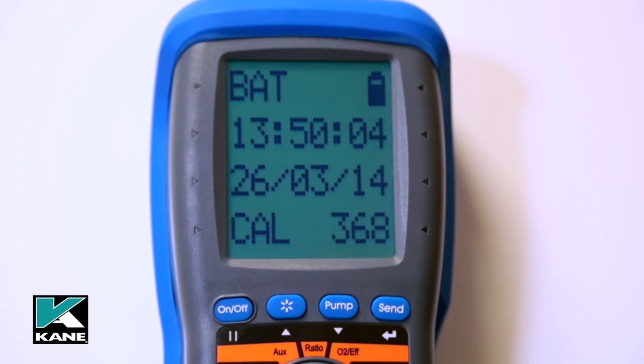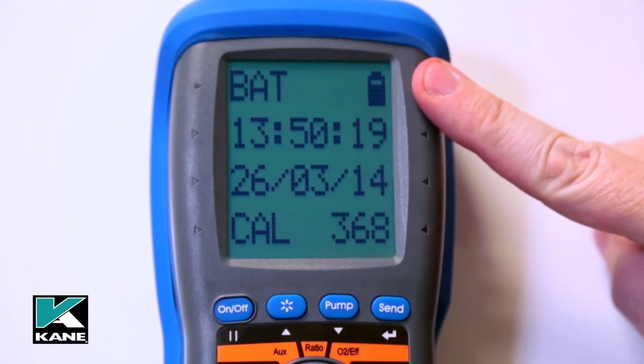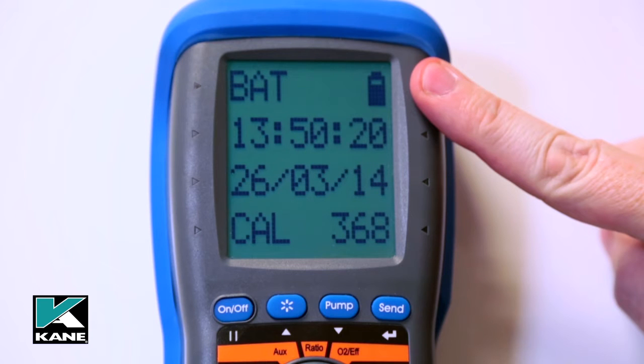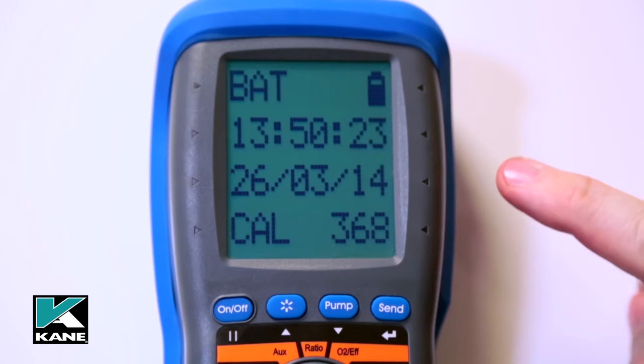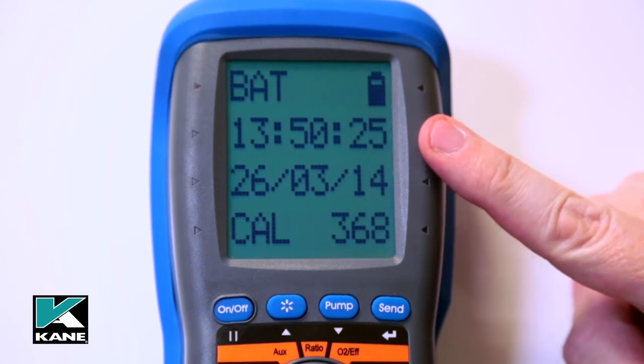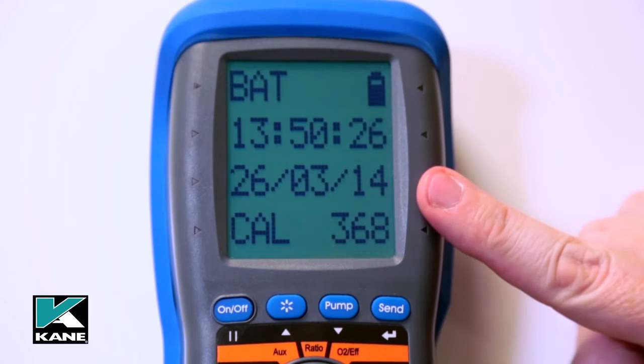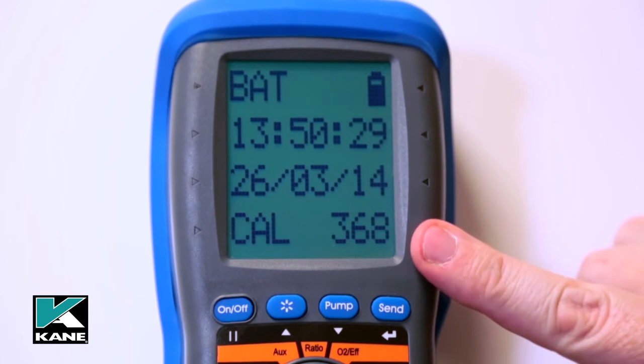If your analyser is out of calibration then any certificates you produce will be invalid. The status display shows battery status — if less than one bar, recharge or replace. Current time and date can both be set via the menu, along with the number of days until recalibration is required.